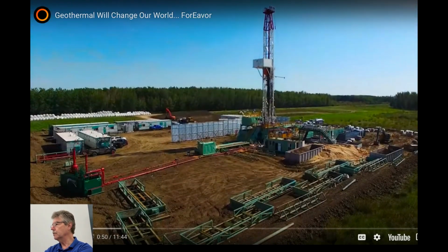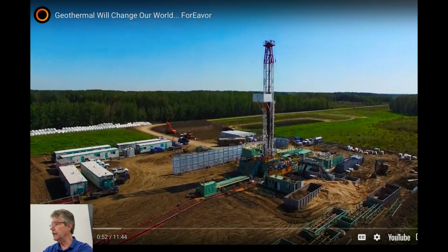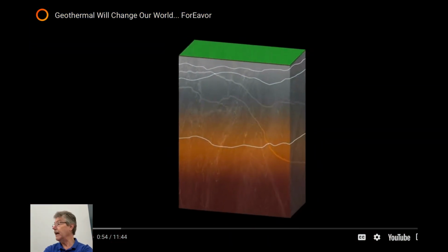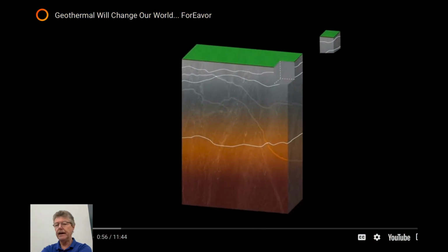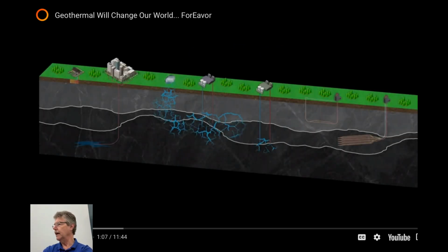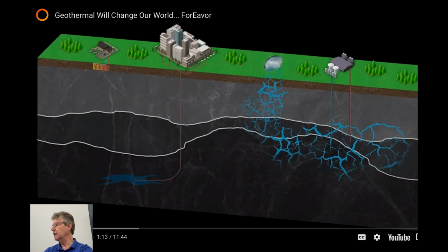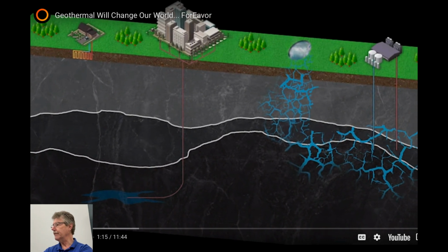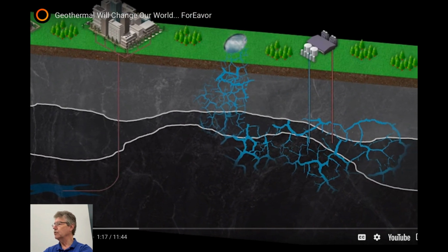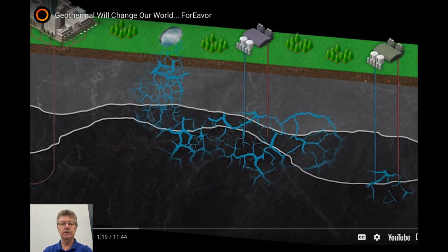It actually milks the geothermal energy, if it's a geothermal heat pump, or the air energy, just like an air conditioner. Because it uses a compressor and fluids, just like an air conditioner or a fridge, it's able to scavenge the thermal energy out of the ambient air. If it's a geothermal heat pump, it scavenges the 55 degree Fahrenheit ground in the summertime to cool the house, and it scavenges that heat in the wintertime, which is still much warmer than the air temperature, to be able to use it.